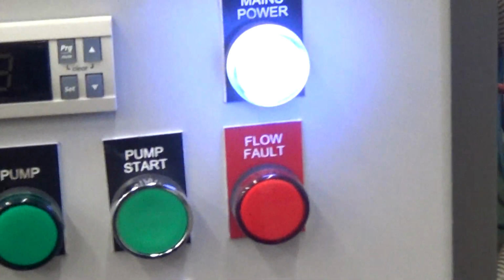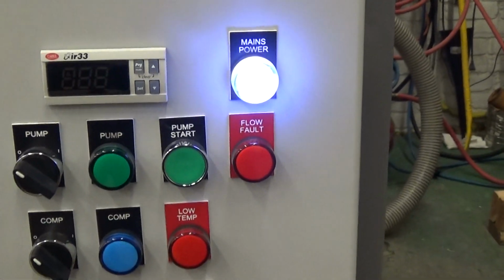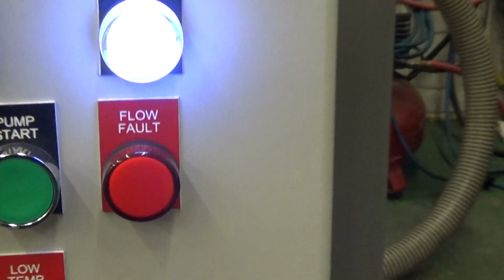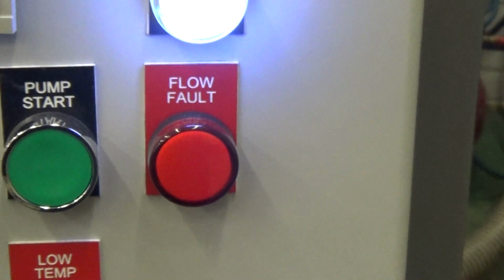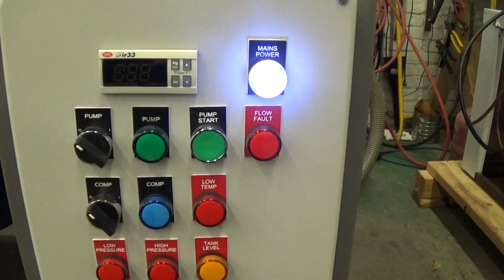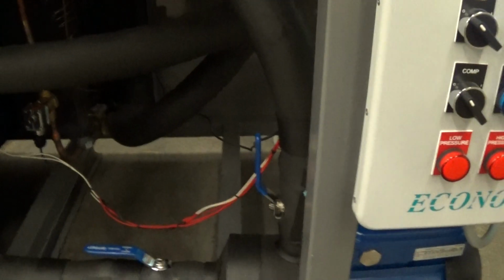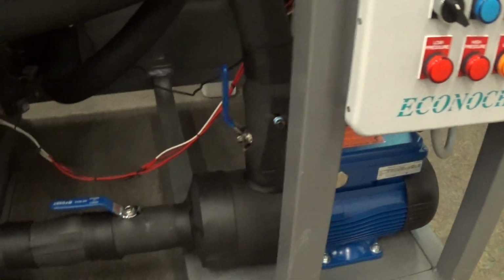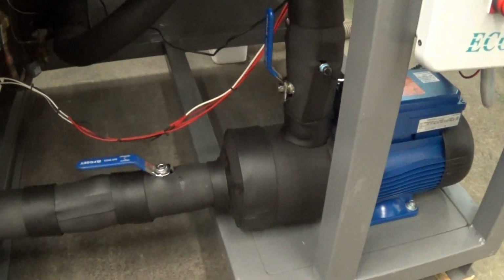Also, you can just see here on the Glycol inlet to the heat exchanger, we have a flow switch. So that's a paddle type flow switch calibrated for each particular chiller. If there is not proper flow, and proper flow is critical for a chiller's heat exchanger, you will get a flow fault here, and that's a super nice feature. Real important to have.